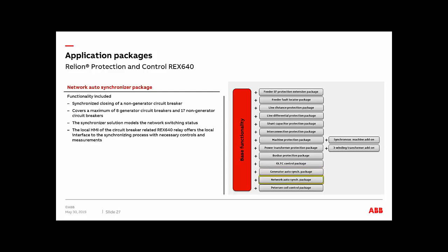Then there's a network auto synchronizer package, and this one will synchronize closing of non-generator circuit breakers or non-source circuit breakers, and it will give you the option of having up to 8 generator circuit breakers and 17 non-generator circuit breakers. This function as well supports the manual, semi-automatic, and automatic synchronizing.